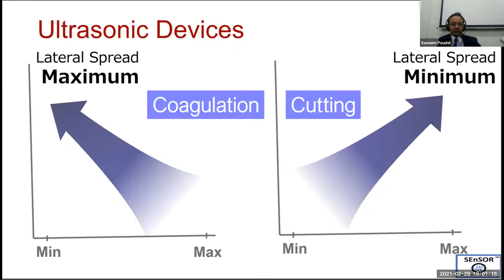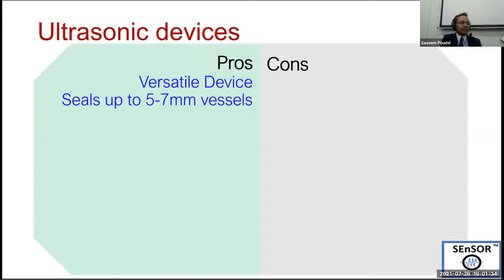Besides the button you choose, you can also influence the efficiency of tissue cutting by how tightly you squeeze the handle, so how tightly the active blade is sitting on the tissue pad, or whether you are lifting the tissue or applying tension on the tissue. Pros and cons: the ultrasonic device is very versatile. Historically it sealed up to 5 millimeters, and newer devices can seal up to 7 millimeters. There is minimal spread of energy through the patient's body. There is no smoke. There is a mist and spray, but there is no smoke.